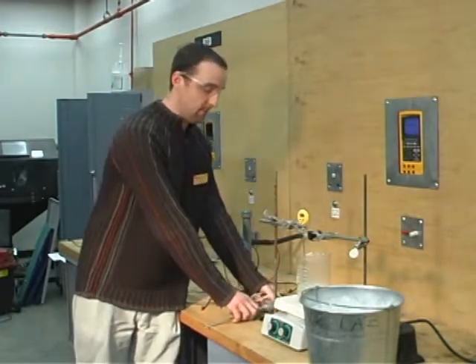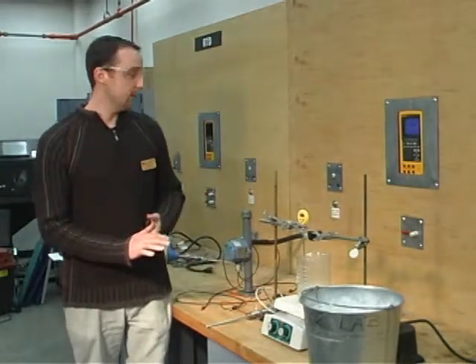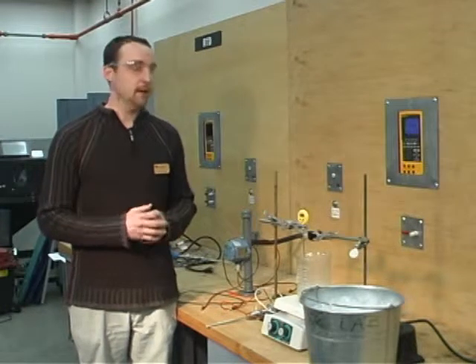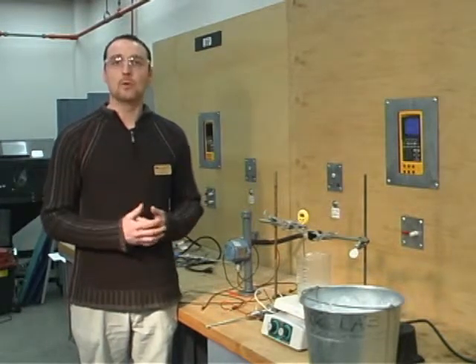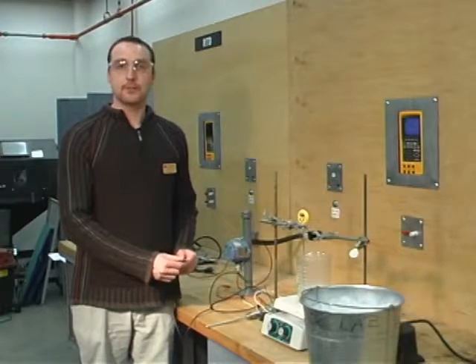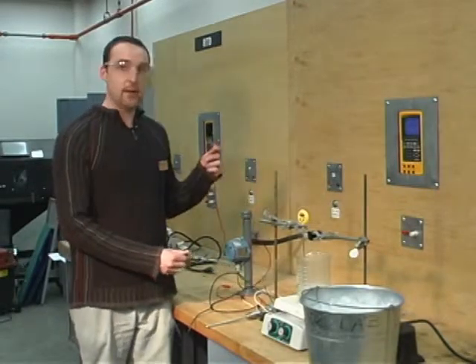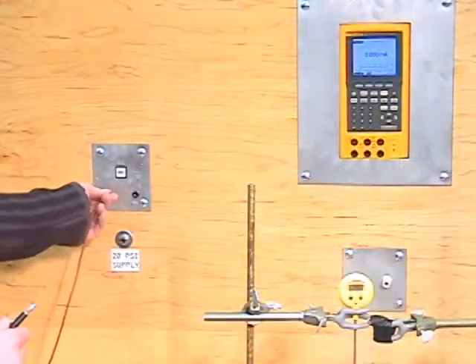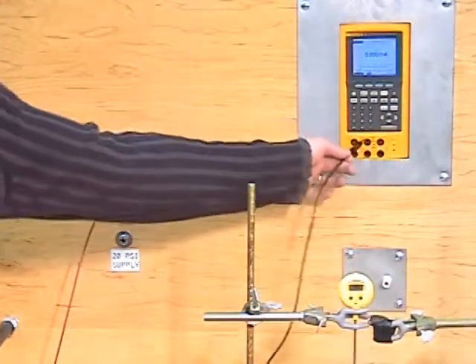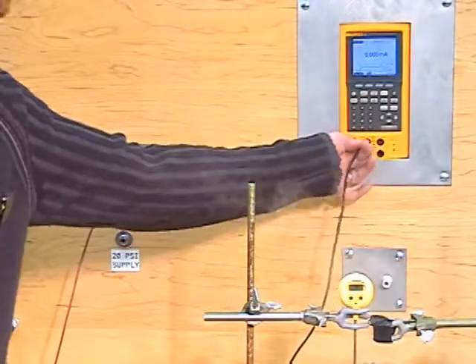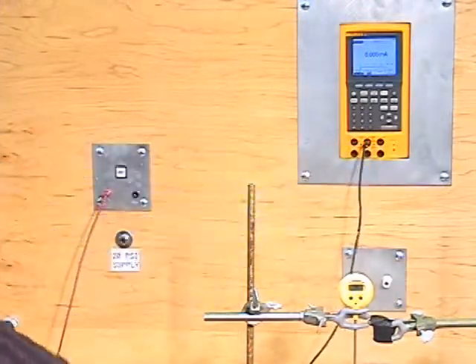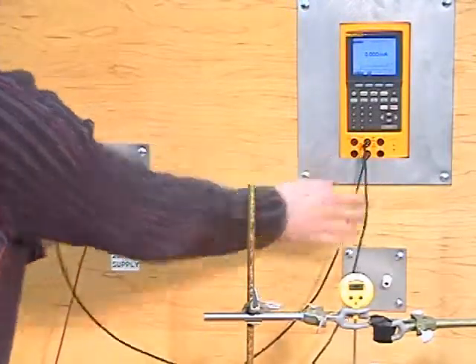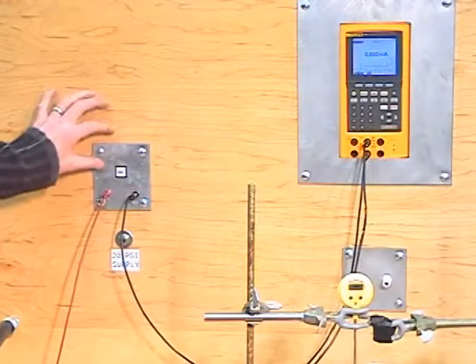We're going to connect our transmitter up to a power supply. It's very important to know that we never connect a transmitter to a live source right away. So when we connect our transmitter, we connect the red and black leads. The red being our positive lead to the positive of our power supply, then to the positive port of our milliamp calibrator into the milliamp slot, then take another wire and close our series loop out of our calibrator to complete our loop of our power supply.